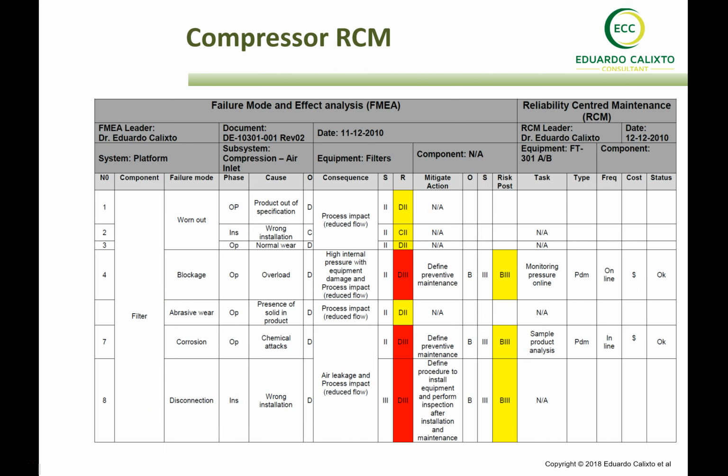We need to be clear that the filter does not have an instantaneous effect in case of failure in the compressor, but that it causes cumulative damage after a period of time. If we do not eliminate the failure, the loss of the function of the filter will be a consequence in a compressor or even a pump.